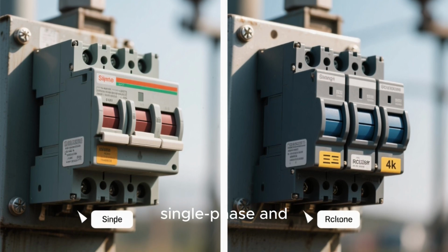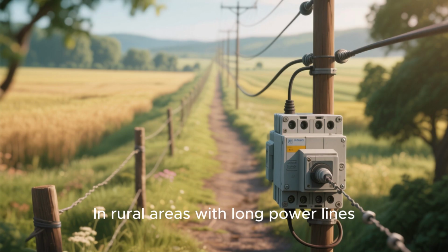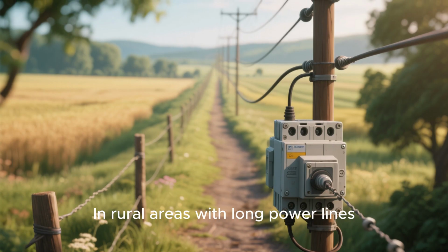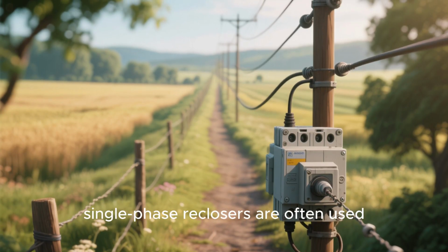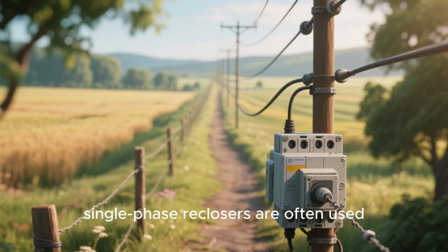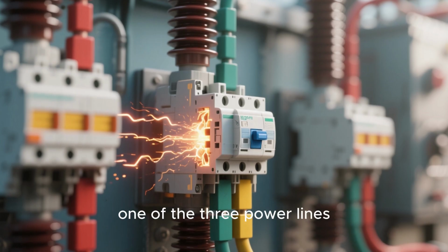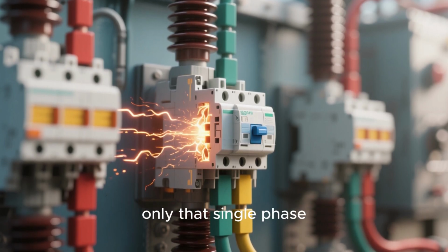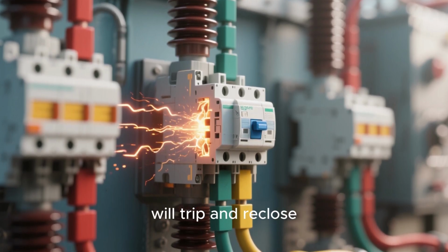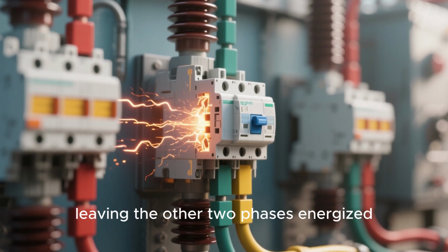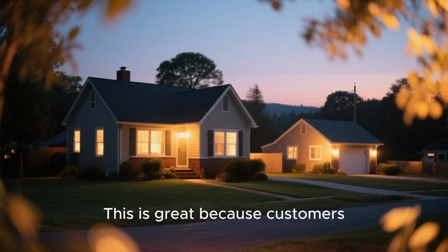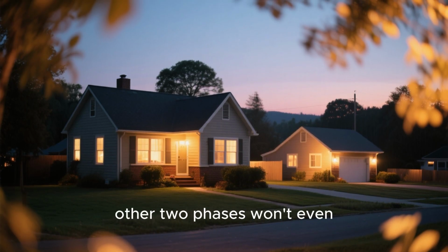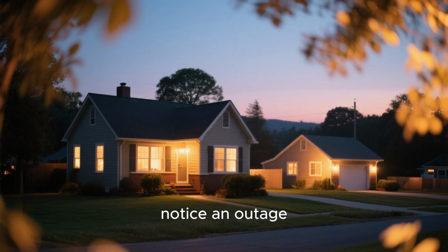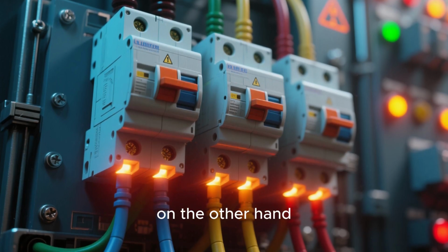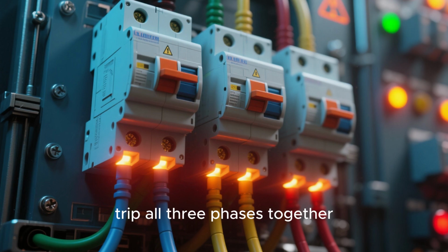The most basic distinction is between single-phase and 3-phase reclosers. In rural areas with long power lines supplying scattered customers, single-phase reclosers are often used. If a fault occurs on only one of the 3 power lines, only that single phase will trip and reclose, leaving the other 2 phases energized. This is great because customers connected to the other 2 phases won't even notice an outage. 3-phase reclosers, on the other hand, trip all 3 phases together.